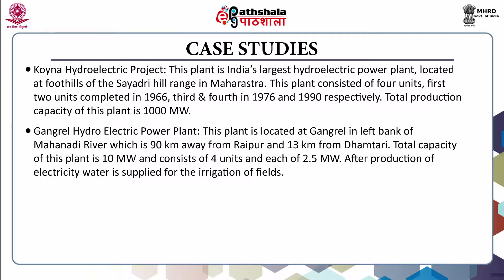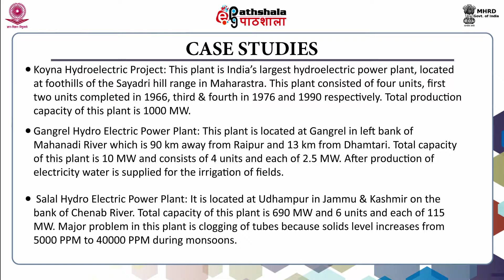Another case study is the Salal hydroelectric power plant, located in Udhampur, Jammu and Kashmir, on the bank of the Chenab river. Its total capacity is 690 megawatts, with 6 units of 115 megawatts each. A major problem in this plant is clogging of tubes, because the silt level increases from 5000 ppm to 40,000 ppm during monsoons.